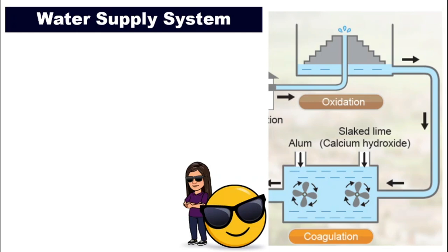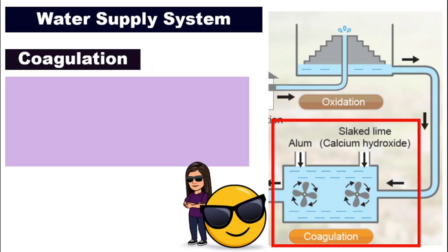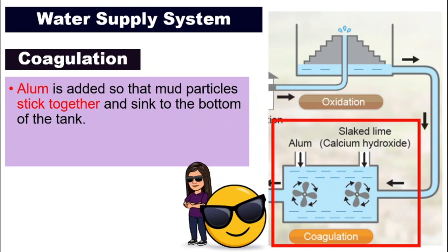After that, the water will then be channeled to the next tank called the coagulation tank. In this tank, we will add in two different things: one is alum, and the second will be slaked lime or calcium hydroxide. The alum will function to make all the mud particles in the water stick together. The mud that was not filtered out in the first filtration tank will be able to stick together and form bigger particles or bigger balls, which will become heavier and then sink to the bottom of the tank. So it acts like a super glue for the mud particles.